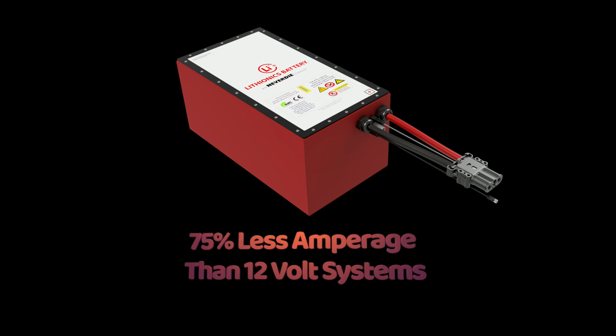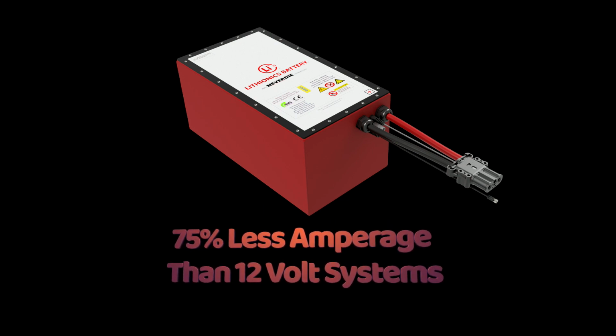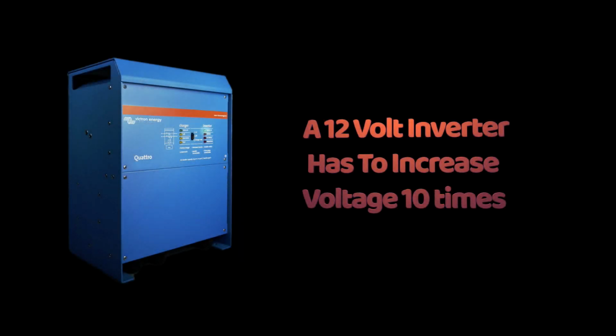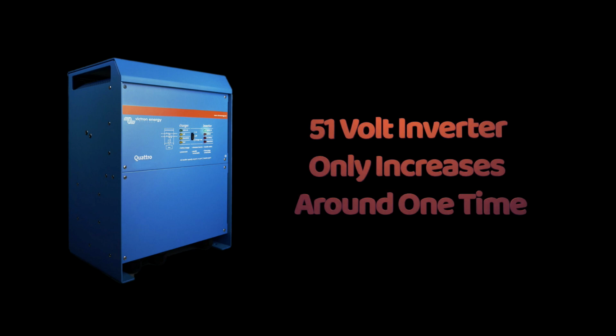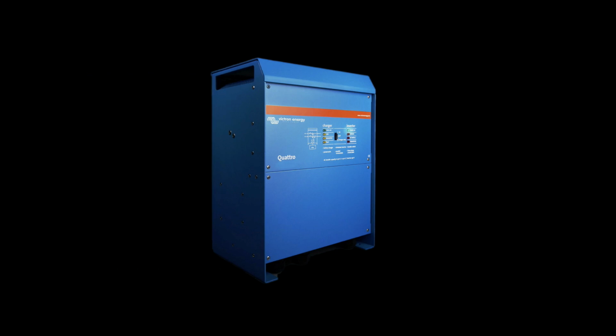Aside from a 51 volt system using 75% less amperage than a 12 volt system, there are inverter benefits as well. Unlike a 12 volt inverter that has to increase voltage 10 times, from 12 volts to 120 volts, a 51 volt inverter only has to increase voltage a little over 1 time to produce 120 volts. This means less work for the inverter and less fan usage to keep the unit cool.